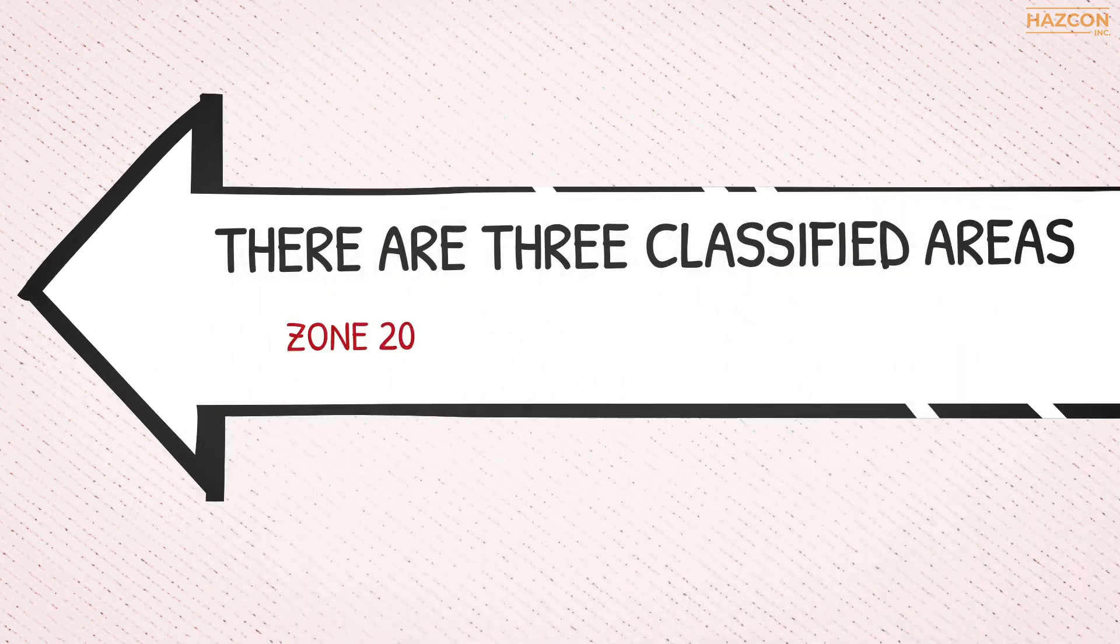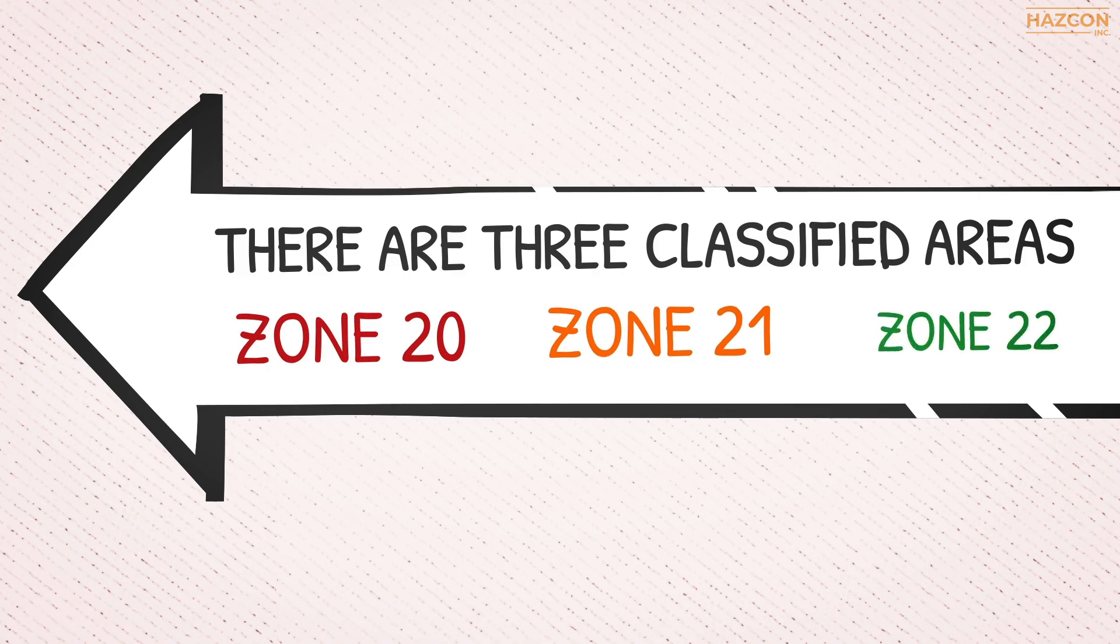America using two different classification systems: the class division and the zone system. There are three classified areas in the zone system that relate to dust explosive areas: Zone 20, Zone 21, and Zone 22.